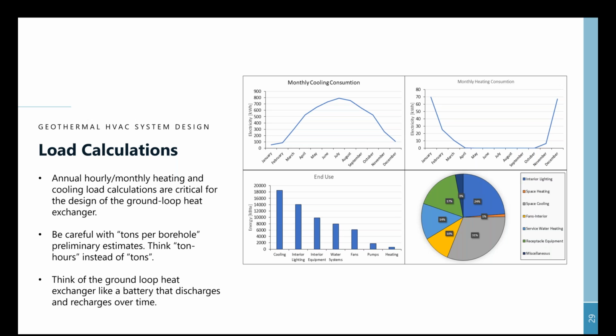One thing to be careful of in designing a geothermal system is that often, when a project is still conceptual, you may not even have architectural drawings—just a general idea of the building and its size. Sometimes you'll hear the idea of how many tons per borehole you'll get from your geothermal field. It's okay early on to make these kinds of estimates, but keep in mind we're not really looking at tons per borehole so much as ton hours—what is the annual aggregate load you're dealing with? I find a good way to think about ground loop heat exchangers is that they're kind of like a battery.